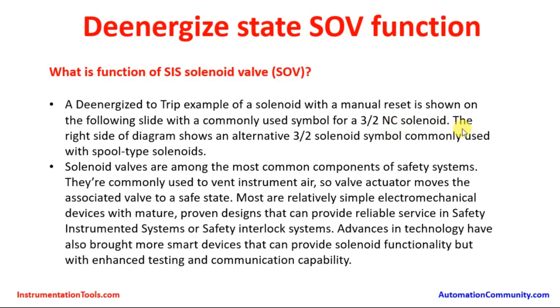NC stands for normally closed. The right side of the diagram shows an alternative 3-by-2 solenoid symbol commonly used with spool-type solenoids — one type commonly used across industries. Solenoid valves are among the most common components in safety systems. They are commonly used to vent instrument air so the valve actuator moves the associated valve to a safe state. Most are relatively simple electromechanical devices with mature, proven designs that can provide reliable service in safety instrumented systems or safety interlock systems.